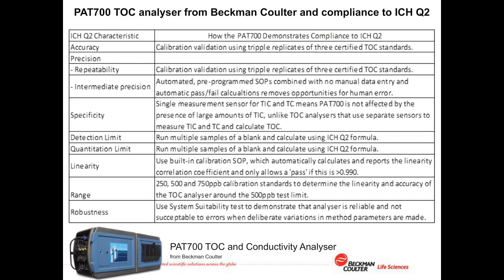Basically, if an online analyzer's data is to be used to reduce the financial burden of QC laboratory testing or to provide release data, then it should be validated as completely as a laboratory TOC analyzer would be. ICH Q2 provides sufficient evidence acceptable to regulatory inspectors from the United States, European, and Japanese regulatory bodies, allowing the online analyzer data to reduce or eliminate the need for QC lab TOC testing. That's why it's important.